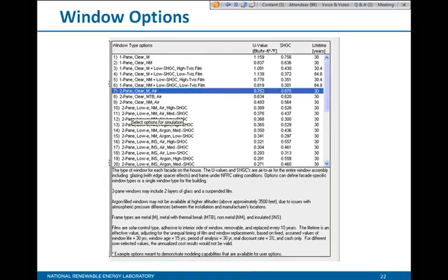Good question. We got these numbers along with the modeling database that the Efficient Windows Collaborative used. And in the software, there's an NFRC summer condition and an NFRC winter condition. I would have to go back and double check this, but my hunch is that the U factors are based on the winter condition and the solar heat gain coefficients are based on summer. I believe that's the way it's done because that's when those two factors would have their greater influence respectively.